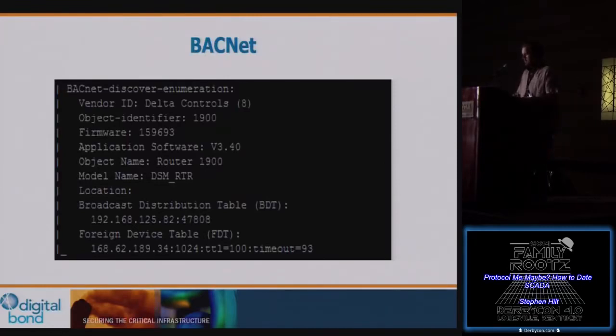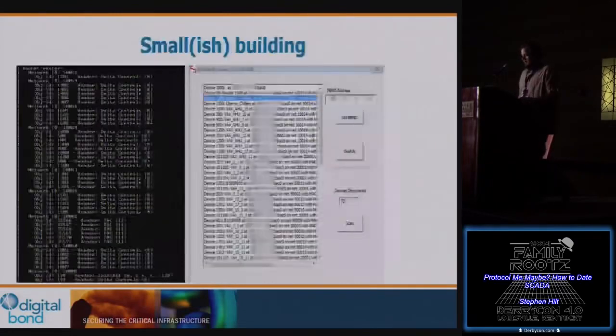And also, there's a device joined as a foreign device. Foreign devices do have timeouts and time to lives as well. So you can join it with a really short time to live, and it'll delete itself, usually. Sometimes you're in there forever, and it keeps giving you information about the device forever.